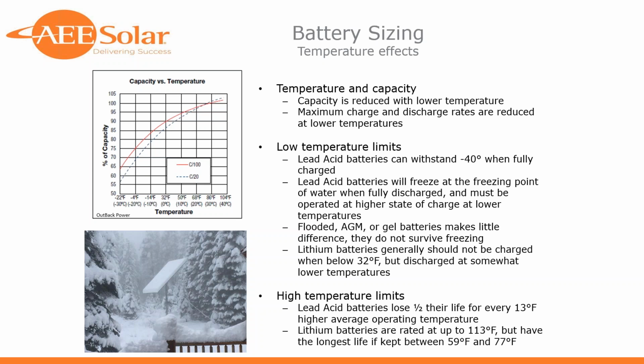And remember that batteries are fairly massive items, and so the battery temperature itself does not cycle as much as your ambient temperature. So if you're at 120 during the day and 80 at night, it's going to be an average temperature of 100 degrees, and the battery is not going to vary more than a few degrees per day. So you're not looking at the peak temperatures, you're looking at the average temperature of where that battery is.